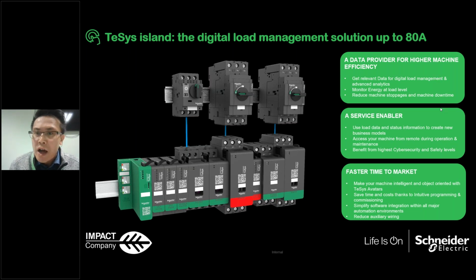So it is a data provider for high machine efficiency. We can get the relevant data for digital load management. We can also monitor the energy at load level. It is not the overall consumption for the panels, but the individual load energy, meaning the individual motors, so that you can identify the performance or the energy consumption of each individual load. It is also a service enabler, so you can use the load data and status to create a new business model. Because you have the data, you know the performance, you know the trip, you know everything about the motor. So you can build a service business, and a lot of different business models with this data. And you can access your machine remotely during operation and maintenance.